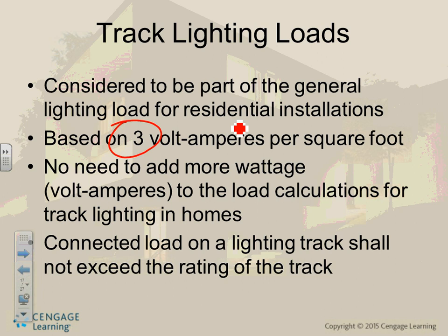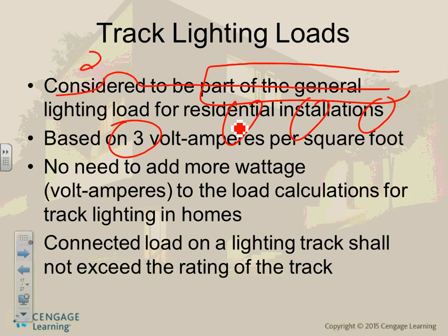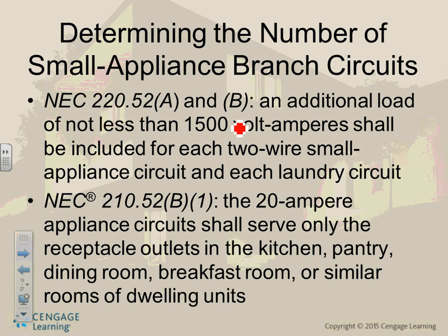If you have track lights, here's a track light with heads here, okay, the load cannot exceed what the track light is rated for. So if you're feeding it from a 20 amp circuit, obviously anything that you put here shall not exceed 20 amps. It says you can't exceed what the track light is rated for.